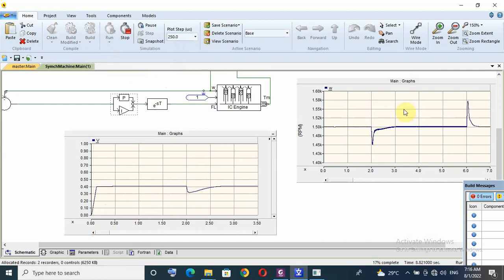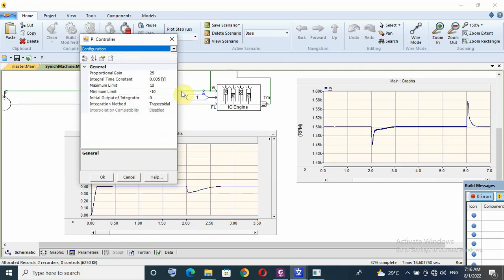And as you can see here also the voltage is decreased because of the speed decrease. I think I don't need to change the integral time, it's okay, but for proportional gain I have to increase again up to 30.